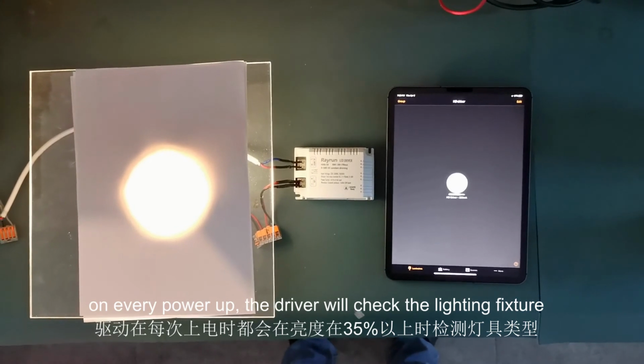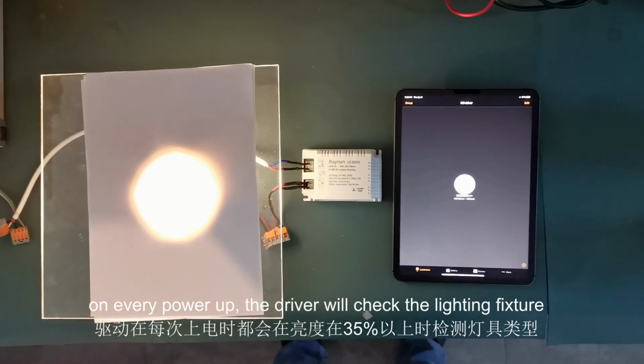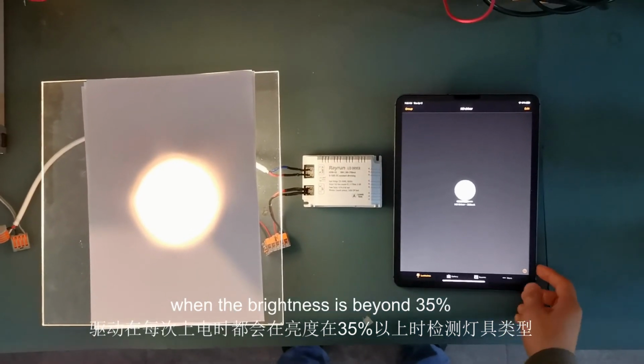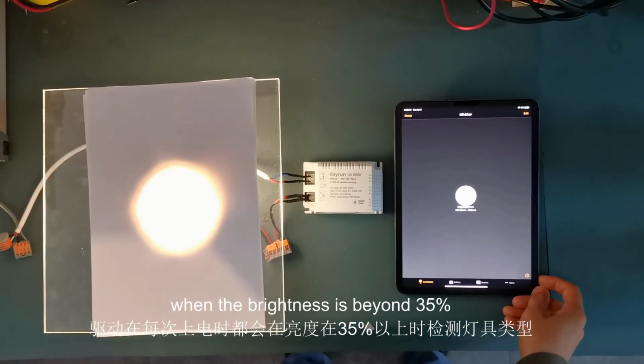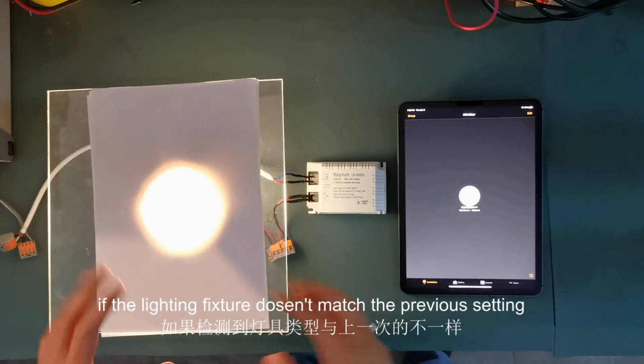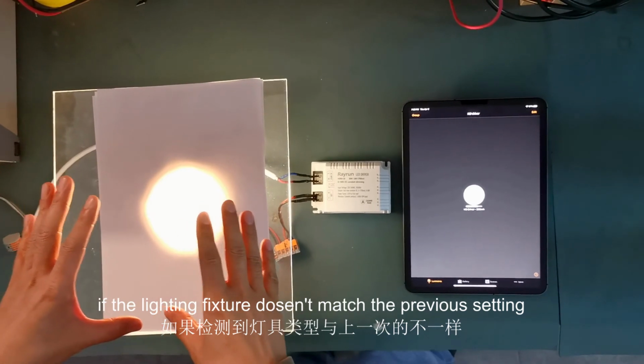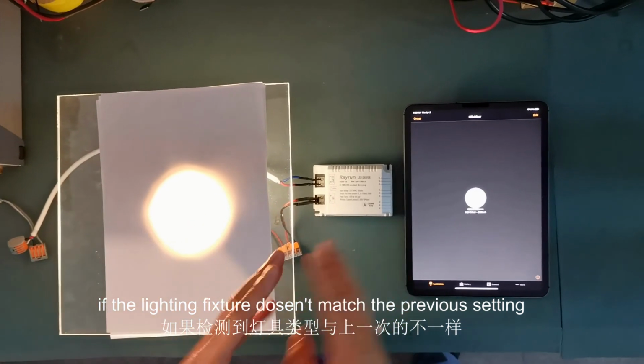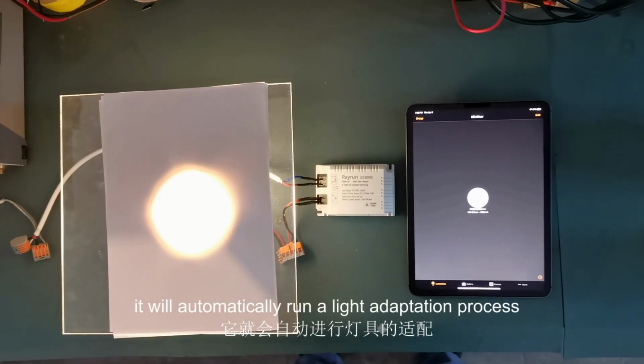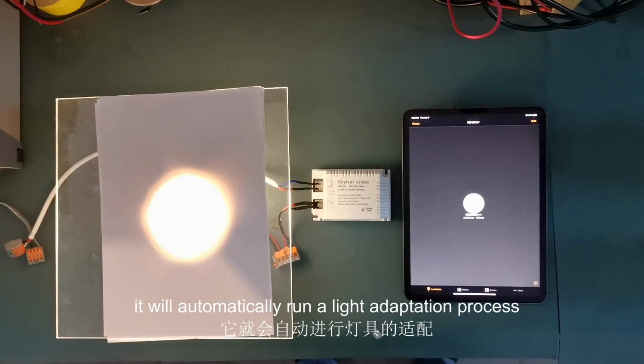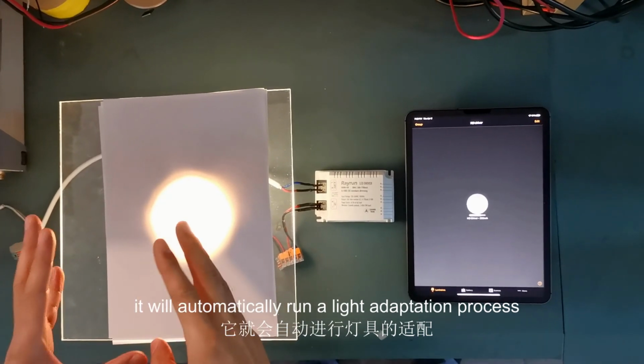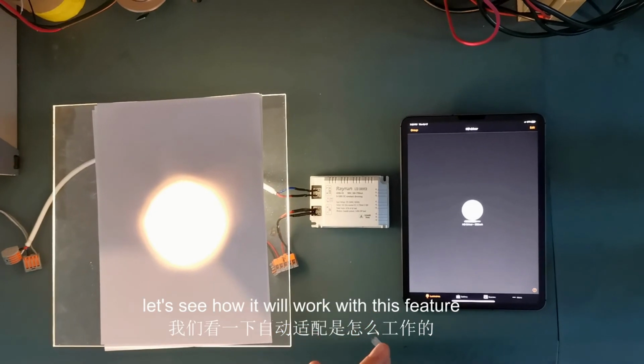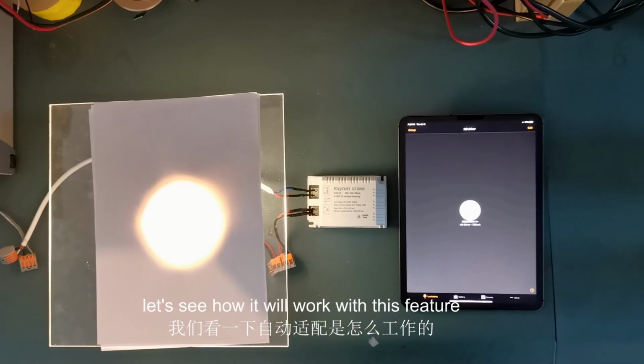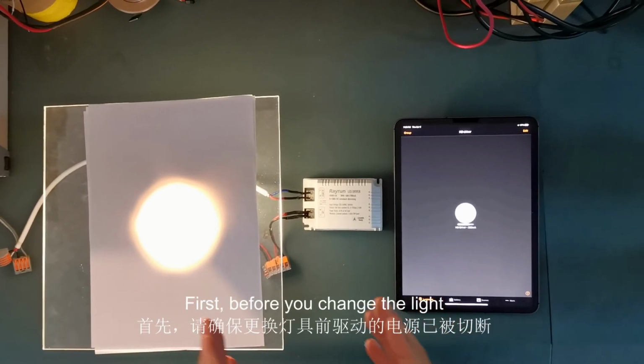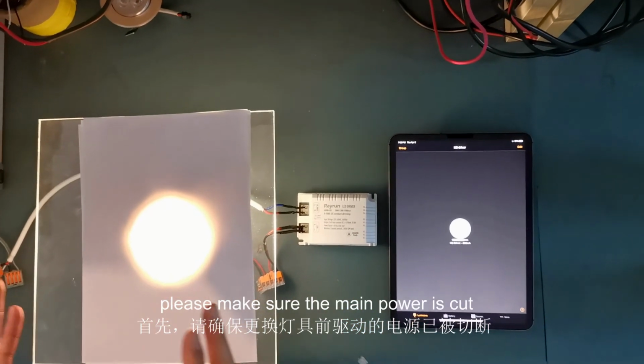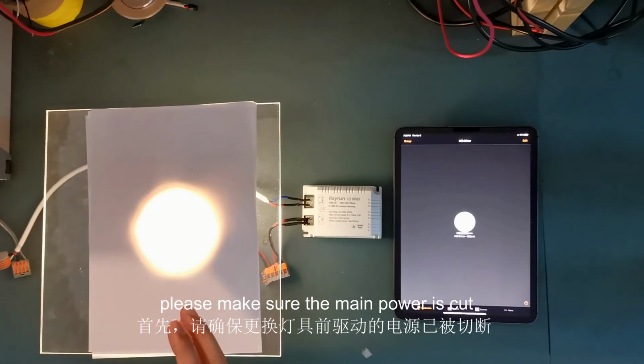On every power up, the driver will check the lighting fixture with brightness beyond 35%, and if the lighting fixture doesn't match the previous setting, it will automatically run the driver light adapt process. Let's see how it works with this feature. First, before you change the light, make sure the main power is cut.